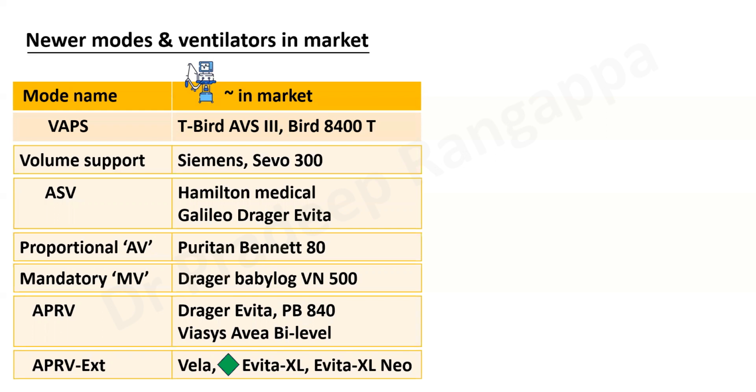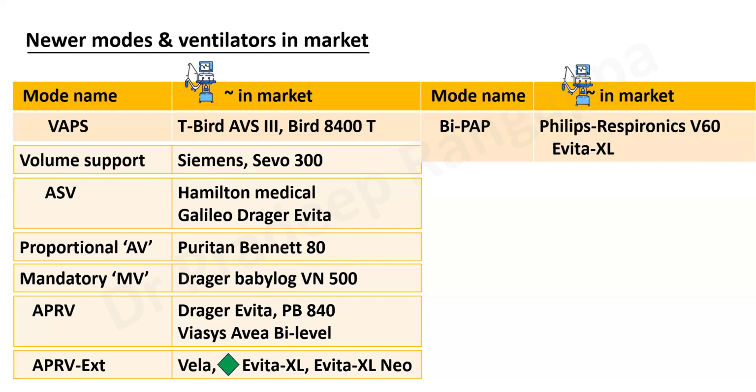So basically, why I'm showing this is that whatever nomenclature you are using is very specific to the ventilator brands that are available. That's why I said at the outset, go and look at your ventilator in your ICU and see what modes it has. And I will show my ventilator and what modes it has. So they're all brand specific, ventilator specific, and some modes are very unique to certain ventilators. And BiPAP, I'm sure most listeners would know, Philips uses this word for most of their modes. BiPAP is more of Philips and Respironics. NAVA is by Servo I.